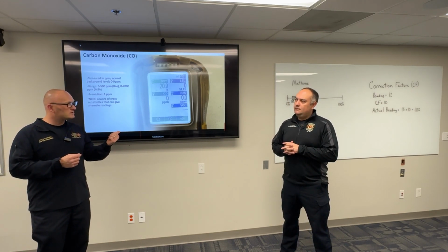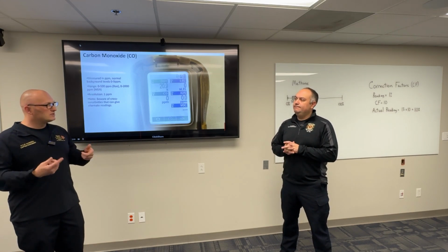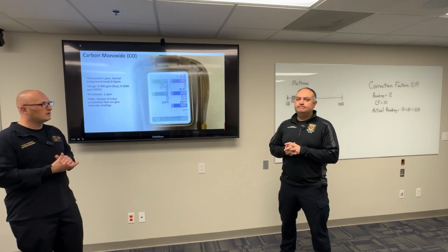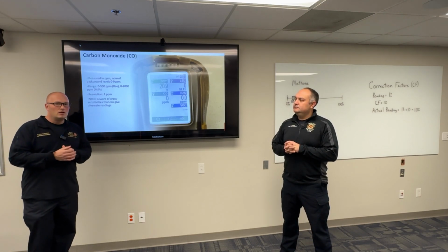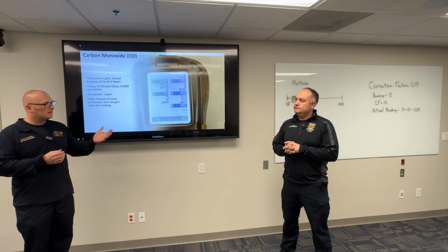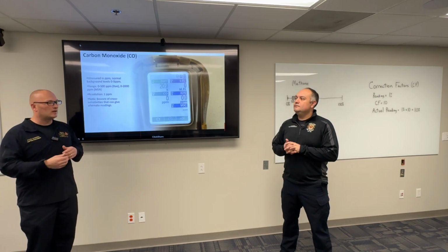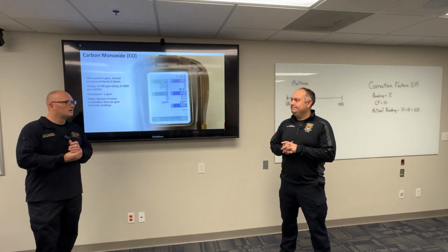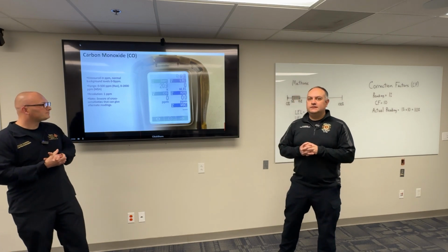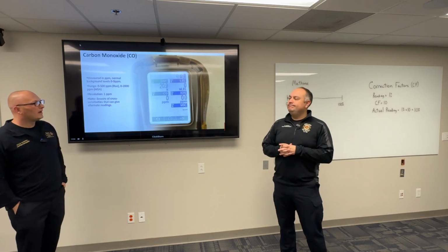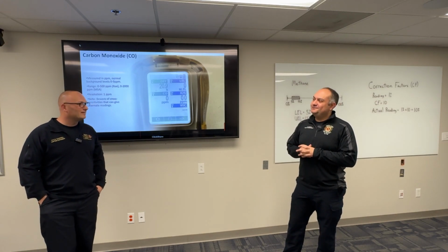We'll turn on the furnace and probably run the hot water if they have a gas hot water heater and furnace, just to kick those up and make sure there's actually nothing going on, and that they're working properly. So we've had a lot of these calls where you might get readings, and it could be something just off with the furnace a little bit, or their stove. Easy fixes, but let Spire come in and check those things out. Yeah, Spire's a good resource for these calls. Oh yeah. Think about hookah pipes and who knows, anything can cause readings.